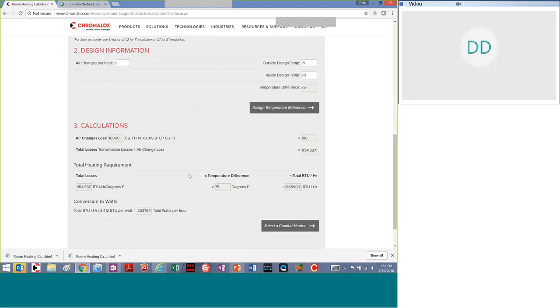So I've already made all the changes. We kept it the same. So this is essentially that trailer or warehouse. Well, we're at 253, or I'm sorry, 25,000 watts. Well, that's easy. That's two 12 kW HVHs. And that makes a lot of sense. You put one in each corner. Yeah, that's pretty easy, pretty simple. You could get the answer to them in less than 5 minutes.